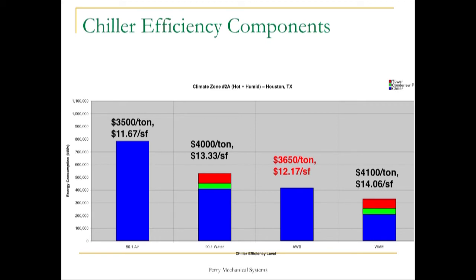This doesn't take into effect any electrical costs. This is purely mechanical. So obviously, as you get more efficient, your electrical costs really should come down a little bit as well. But you're looking at $11.67 a square foot, and about 800,000 kilowatt hours of consumption on this building with your traditional methodologies. If you go water-cooled, you're looking at $4,000 a ton. It's going to add about $500 a ton, or $13.33 a square foot.